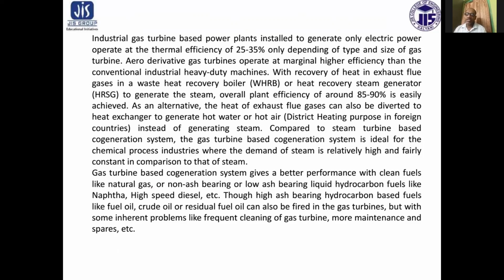With recovery of heat in exhaust flue gases in a waste heat recovery boiler or heat recovery steam generator to generate steam, an overall plant efficiency of around 85 to 90% is easily achieved. As an alternative, the heat of exhaust flue gas can also be diverted to a heat exchanger to generate hot water and hot air instead of generating steam. Compared to steam turbine based cogeneration systems, the gas turbine based cogeneration system is ideal for chemical process industries where the demand for steam is relatively high and fairly constant in comparison to that of steam.